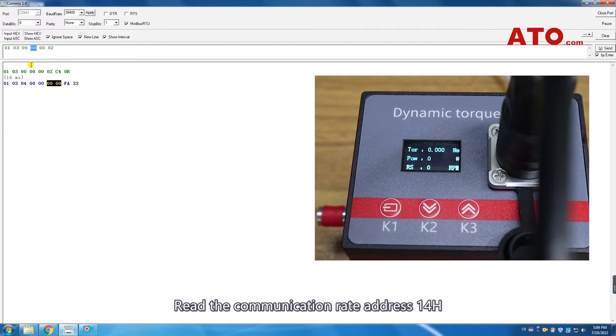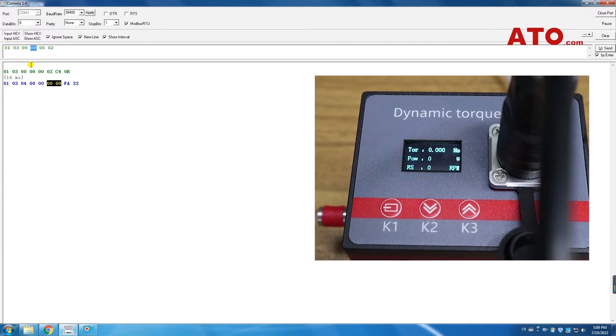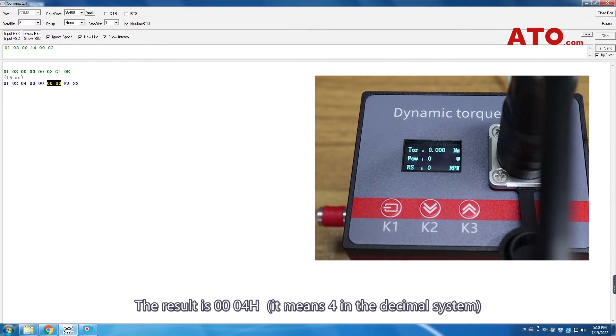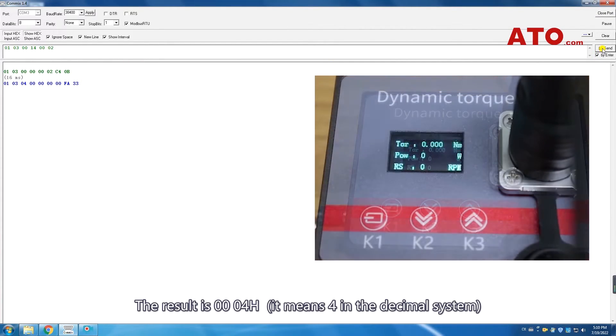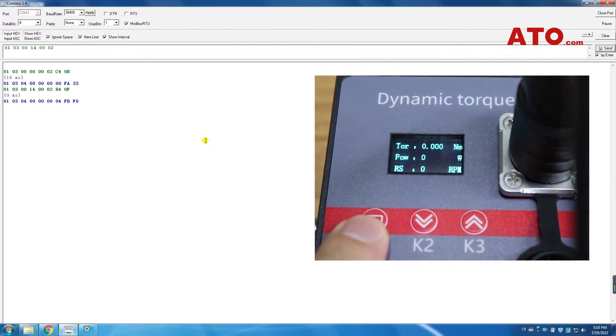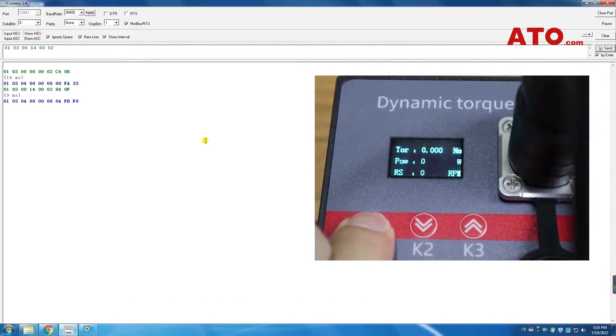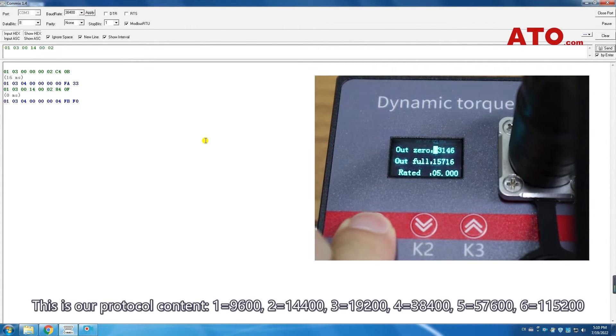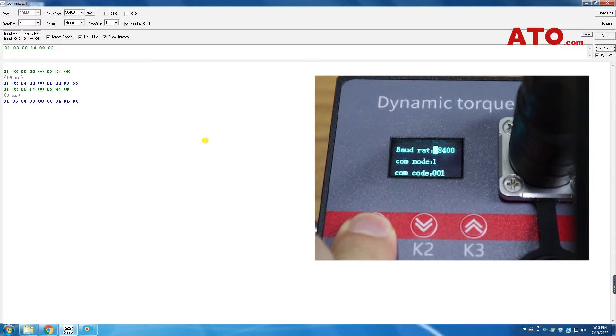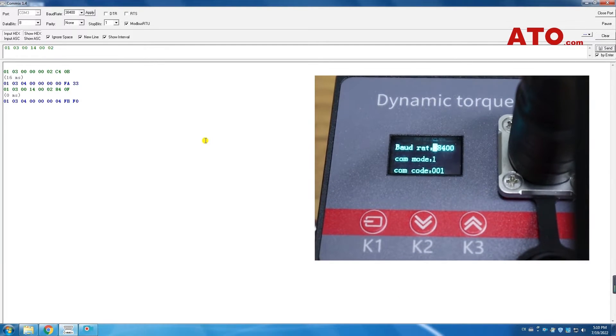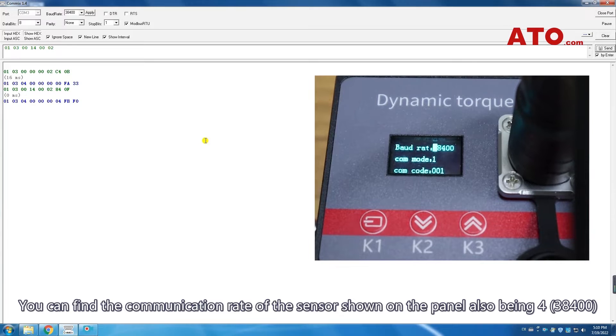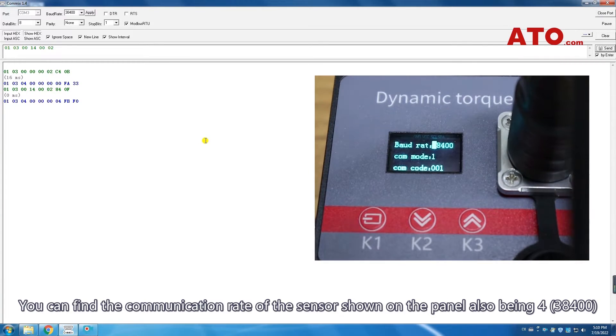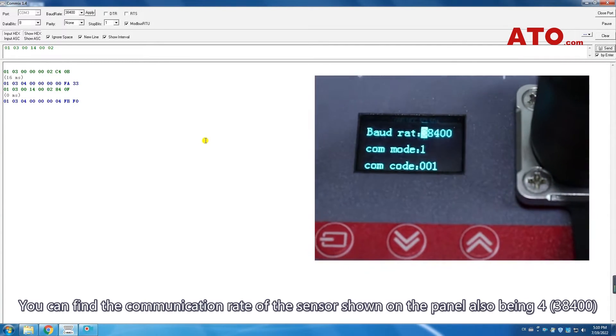Read the communication rate address 14H. The result is 000004H. It means 4 in the decimal system. This is our protocol content. You can find the communication rate of the sensor shown on the panel is also 4, which is 38400.